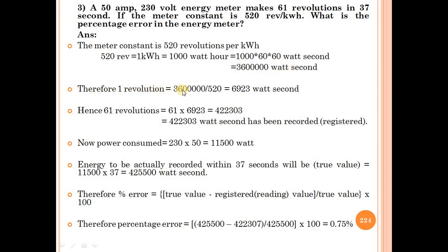Therefore, 1 revolution = 3,600,000 / 520 = 6923 watt seconds. For 61 revolutions: 61 × 6923 = 422,303 watt seconds has been recorded and registered by the energy meter.